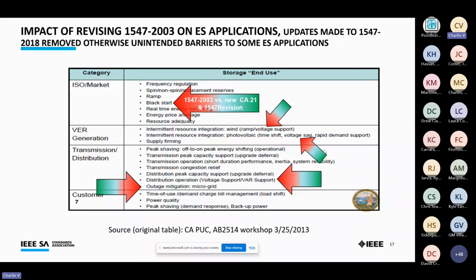So you've got one area in the proposed ruling under preliminary screening criteria that proposed projects not affect the ability of interconnecting utilities to maintain C84.1 ranges, those are the allowable voltage ranges. Inserting a word like negatively affect would leave open the opportunity that these voltage regulating assets, especially under high penetration, should be released to positively affect and support primary voltage distribution regulation, or at least considered, depending on the attributes of your system and the type of voltage regulation equipment and practices by the utilities. But that's just an example to throw out.